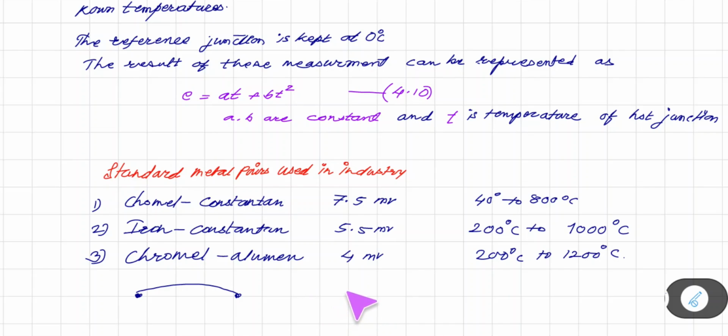Similarly, as long as the junction is at uniform temperature, remember that it does not matter how the junction is made. It may be brazed, spot welded, etc. However, it is crucial for accuracy that the leads of the thermocouple maintain a well-defined composition.